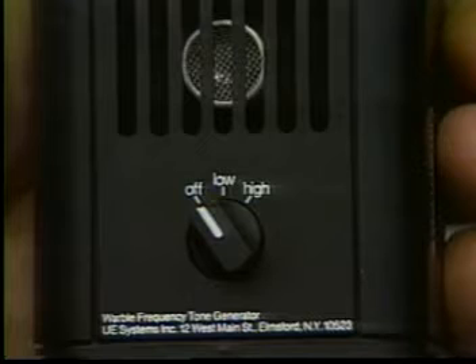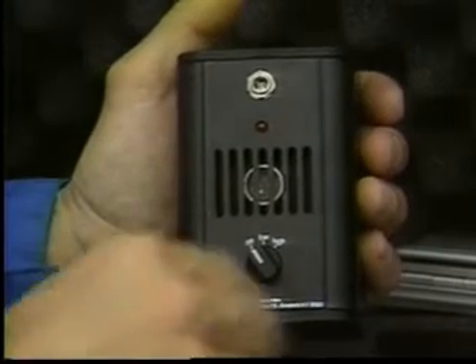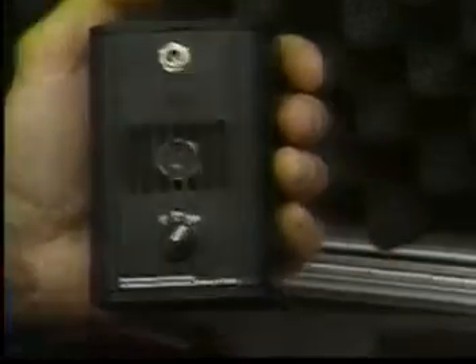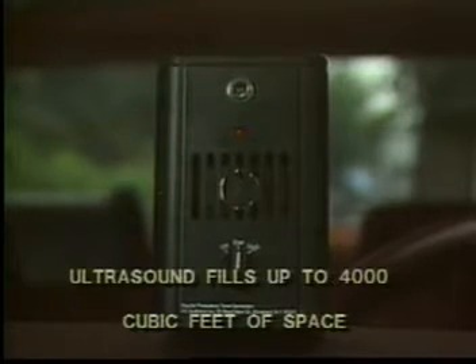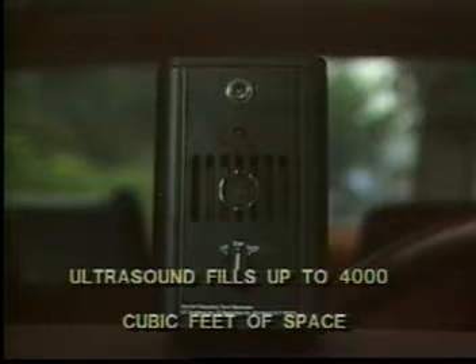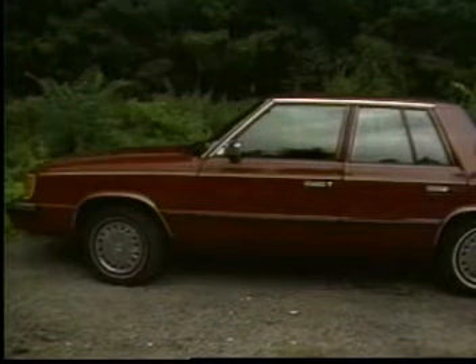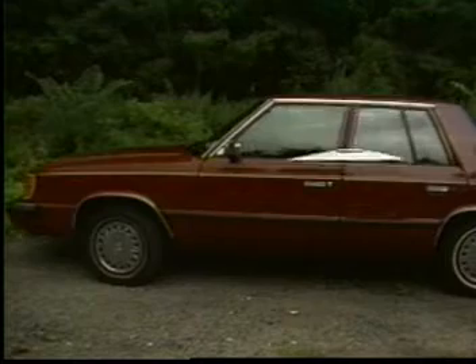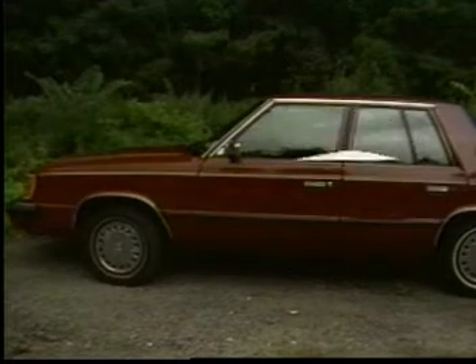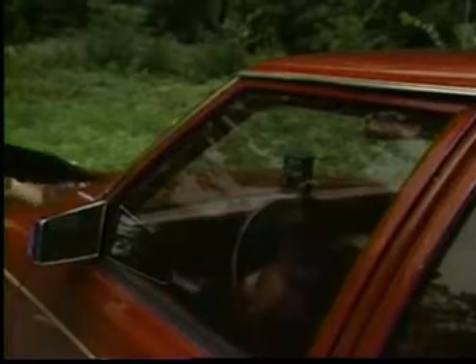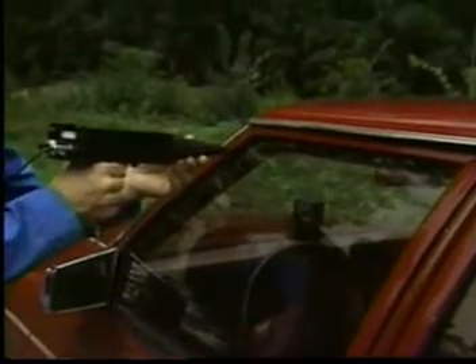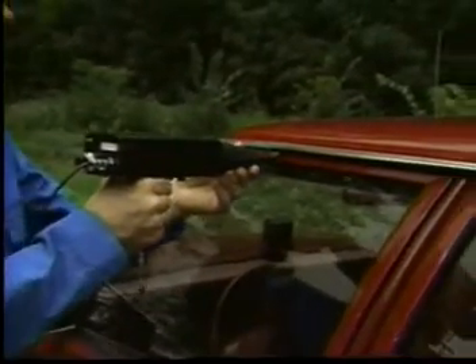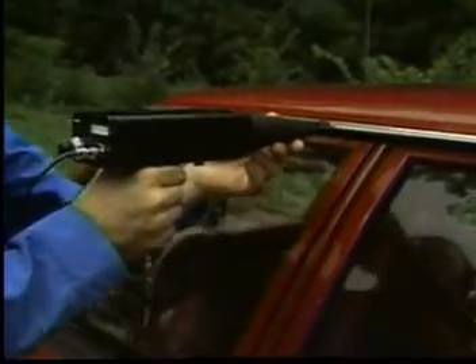Now let's discuss use of the warble tone generator. The tone generation method can be effective in situations when it may be difficult to pressurize or create a vacuum. The tone generator is placed inside the item being tested. Ultrasound is then transmitted, filling up to 4,000 cubic feet of space. Because ultrasound is a shortwave signal, it deflects off solid surfaces, but will penetrate any pinhole leak. The same scanning method described earlier, used on the other side of the test surface, will pick up any escaping ultrasound indicating a leak site.